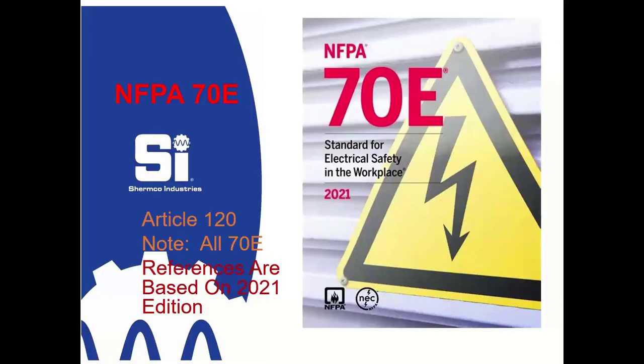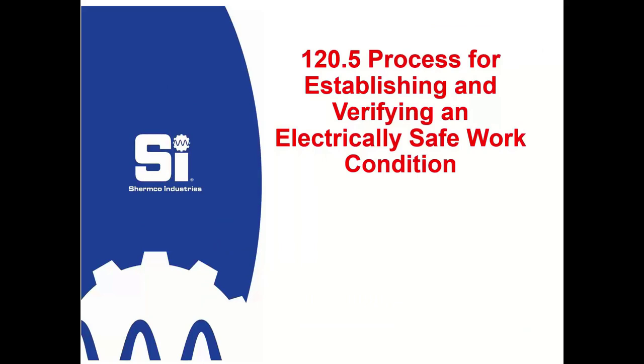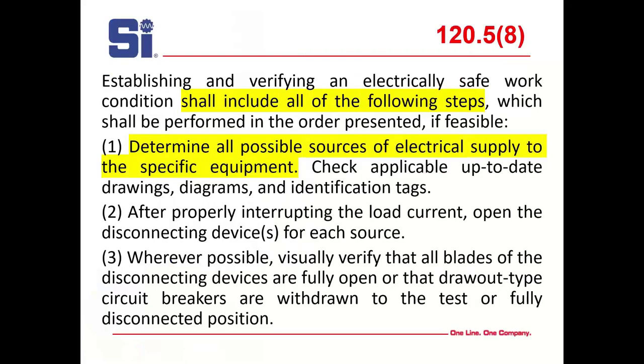Now let's talk about NFPA 70E. I go off the new edition. Most of the information concerning personal protective grounding is in Article 120, Section 120.5. Establishing and verifying an electrically safe work condition shall include the following steps: first, determine all possible sources of electrical supply to the equipment. That could be something you believe is de-energized that is still energized. So you have to check applicable, up-to-date drawings, diagrams, and identification tags — and you have to be careful, this is a big problem.